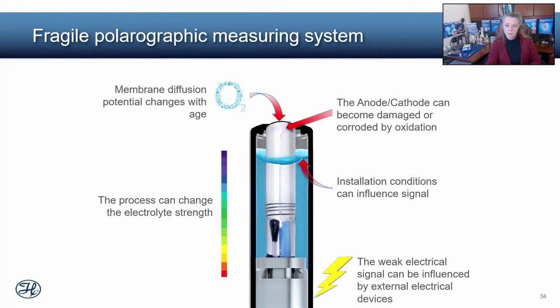Okay. And finally, polarographic probes make nanoamp signals. Nanoamp signals are weak, and that means they're very susceptible to noise from the environment. In fact, so much so that if I was to take a cable and flick it with my finger, and it's a nanoamp signal, and you're watching the display of the reading, you'll actually watch every time I thwack it with my nail, you'll watch a spike in the signal. Well, obviously in a lab, you're probably not going to go around flicking cables. But let me tell you what does happen.